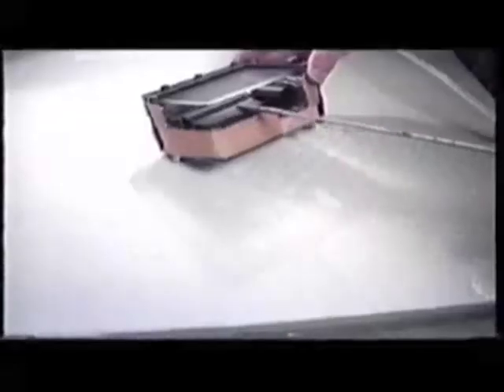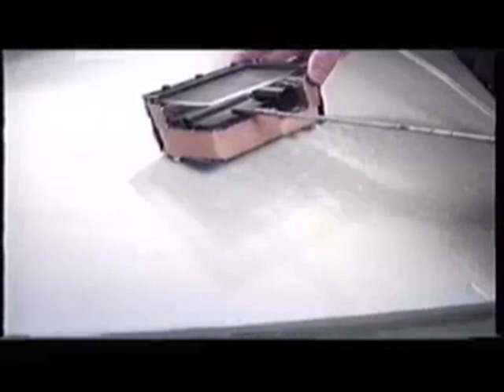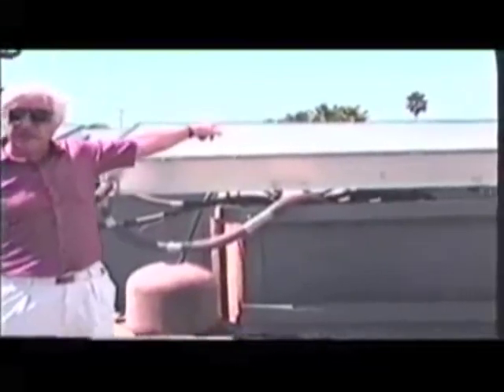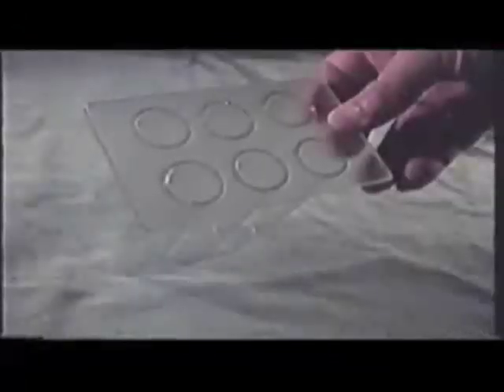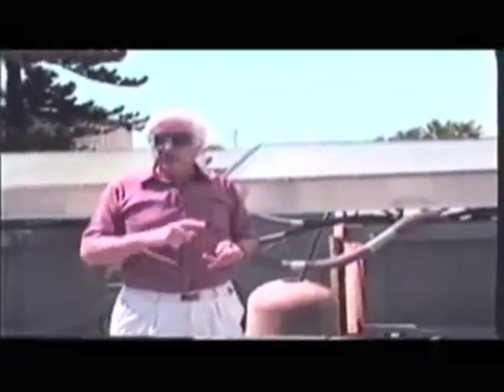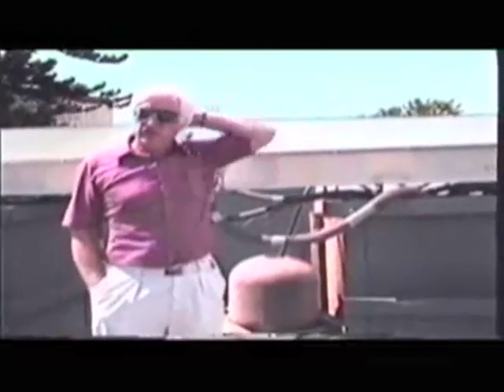The bottom is an absorber, which is a piece of copper metal painted black, or copper tubes through which the water runs and is heated from the absorber. There is simply a box around it and it's a transparent insulator — in fact, a set of baffles that prevent re-radiation of the light and loss of heat from infrared radiation to the sky. So the thing operates on the mode of preventing convection and re-radiation, and therefore allows these collectors to get almost a hundred degrees hotter.